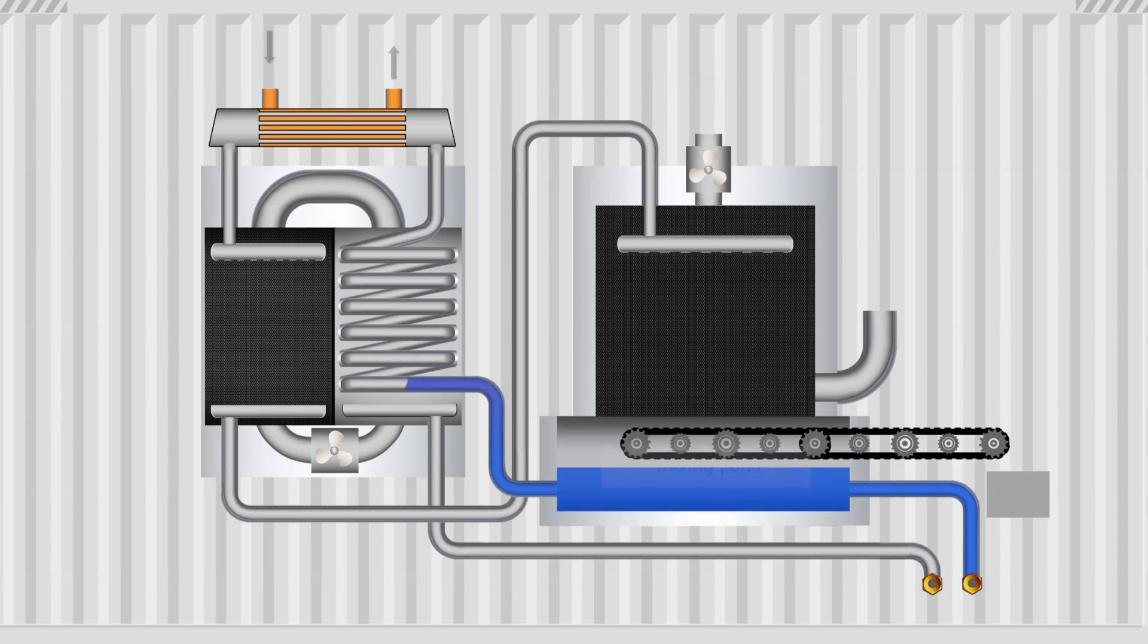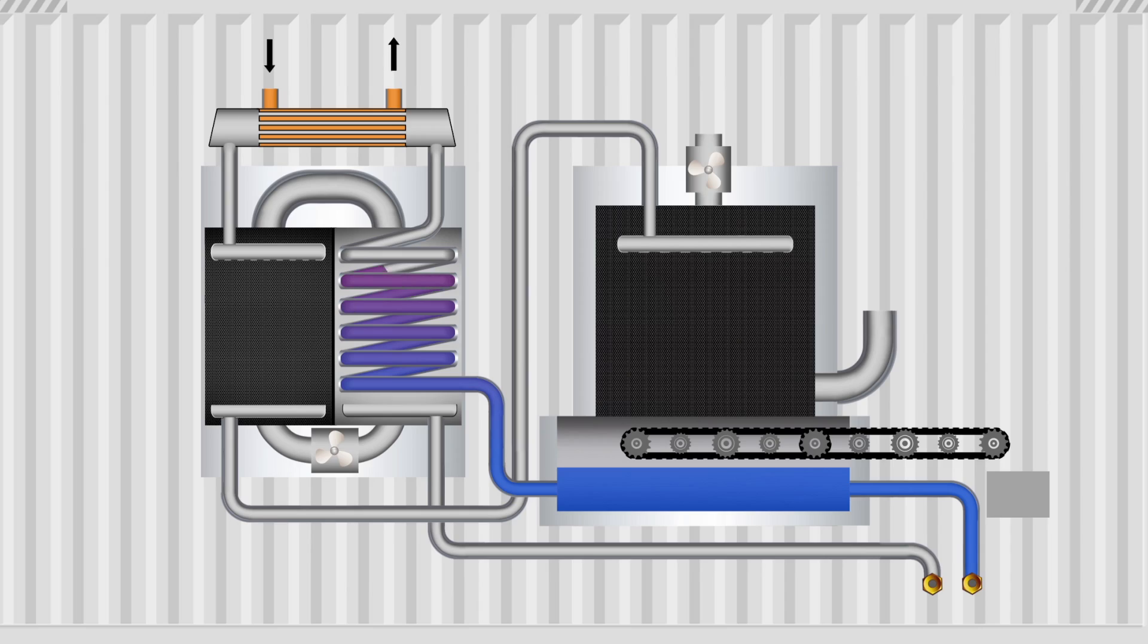North Sea water is fed to the system via the mixing pond. In the mixing pond, the fresh North Sea water mingles with the concentrated one. The North Sea water enters into the evaporation unit. Here it is preheated in the condenser and heated up to a maximum of 95 degrees in the external heat exchanger.